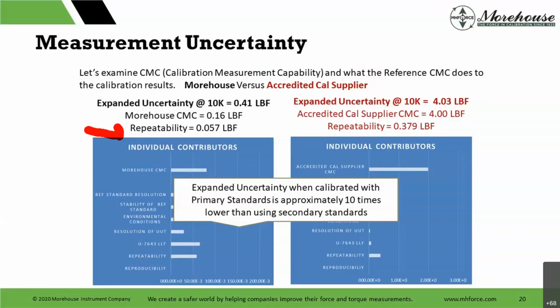All they're doing is operating at 10K when they have their specification as like 0.04%, right? All they're doing here is taking the same things we are, trying to do the same calibration, and at the end of the day, we could put out a reference. We could put out a load cell someone sends us for cal. We could pull it out and send it to you with an expected performance of 0.41 pounds. The other supplier is going to send that same load cell out with a minimum of 4.03 pounds. So about 10 times lower than using secondary standards. And it's just the nature of it. Primary versus secondary. You can look at it any way you want.